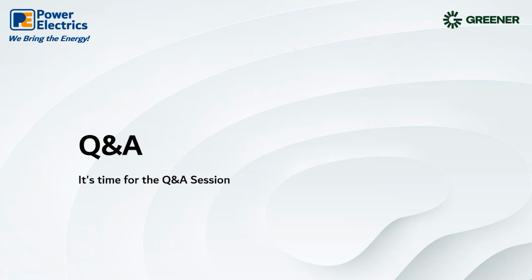It's not quite the same principle as a UPS, but the switching process of the inverters is such that it will act as it. And if you're running in a grid, and Dan might come back in if I've got this one wrong, but if it's acting as a grid shaving mode, then the 0.1, 0.2 of a millisecond switching time will enable it to basically act as a UPS. The advantage with this also is that you can use the energy store systems alongside a grid supply, and then have what we refer to as an active front end generator.